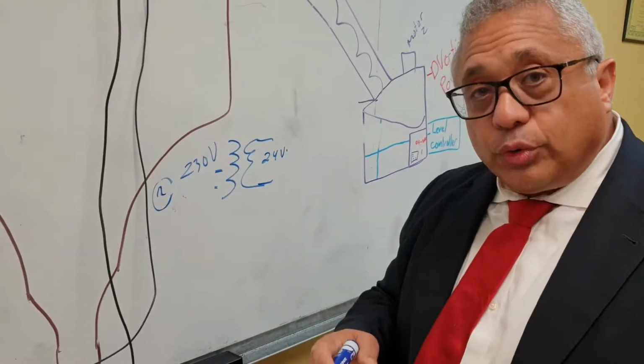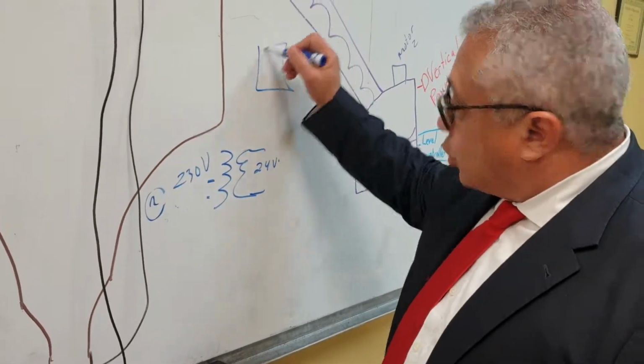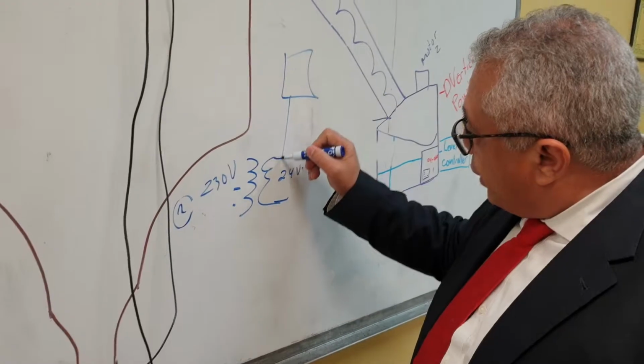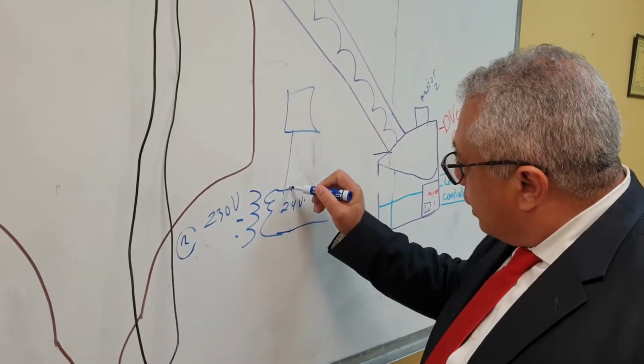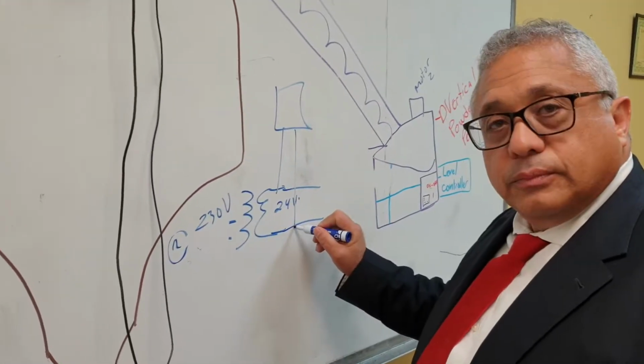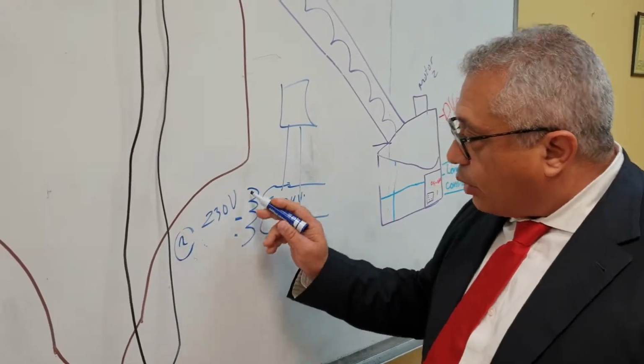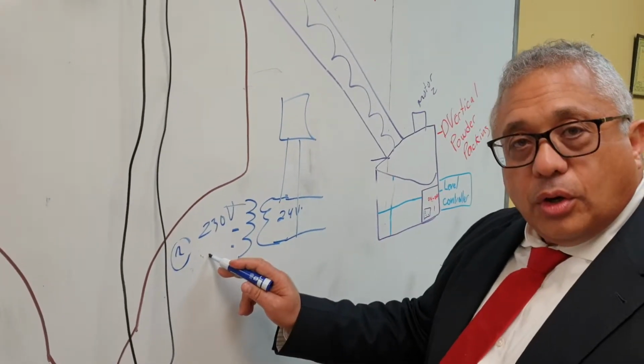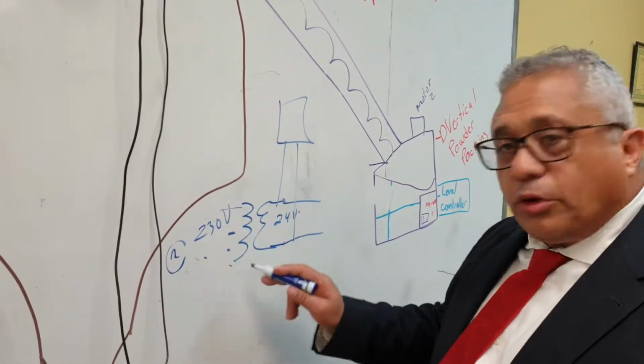Since we didn't have 24 volts, we used our panel and fed 24 volts to these two lines. Once we did it, we found 230 volts on the other side of the transformer, which means the transformer is working.